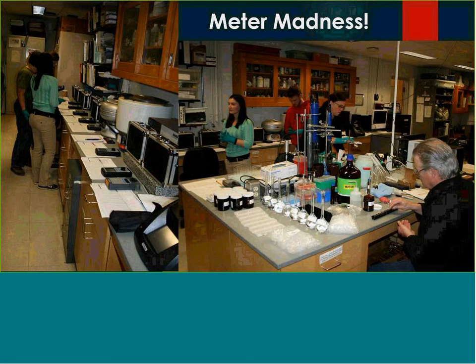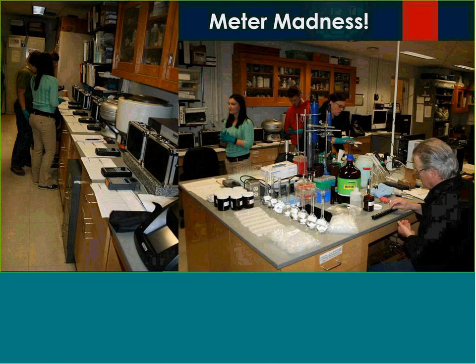For the monitoring group, how do we keep track using these instruments so that our quality assurance is good and we can have reliability in our measurements? One of the things we do is have an annual meter madness calibration event, where we bring all the instruments together and calibrate them all at the same time under the same conditions with the same calibrators, so we have consistency across the region. It makes for a long day, but it's good for quality assurance.